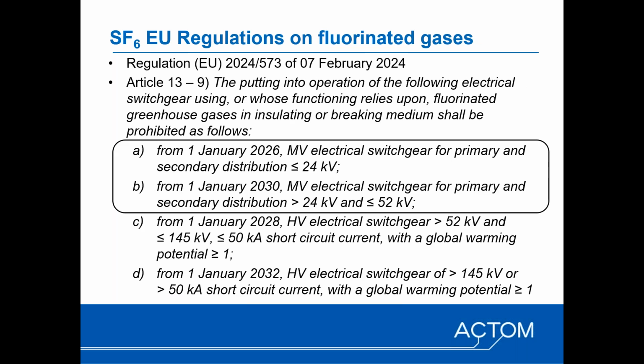Right, so we mentioned we would touch on the EU regulations, obviously not applicable to us directly in South Africa, but it's worth mentioning that this year in February, the latest regulations were published and some defined dates have been published within the regulation. As far as medium voltage equipment is concerned, from 1st of January 2026, no switchgear rated up to 24 kV can use fluorinated gases. And then from 2030 onwards, all other medium voltage switchgear, so up to 52 kV. And there are similar dates for switchgear rated above 52 kV.